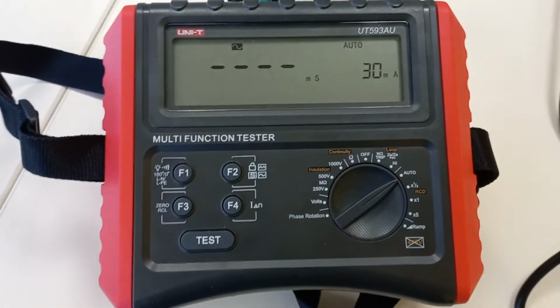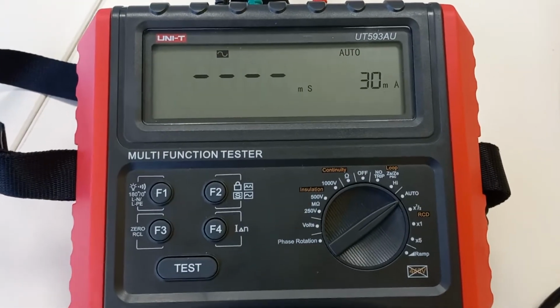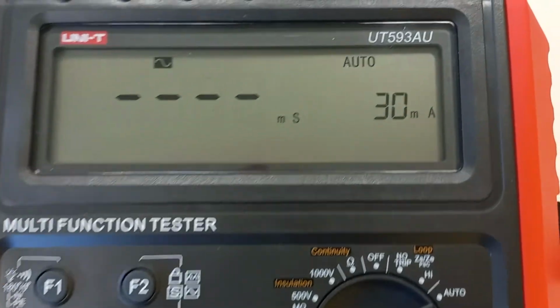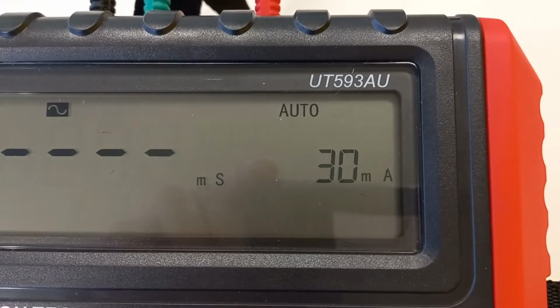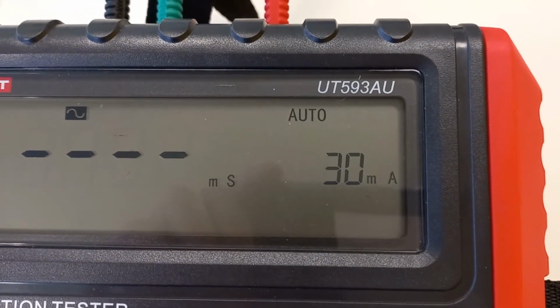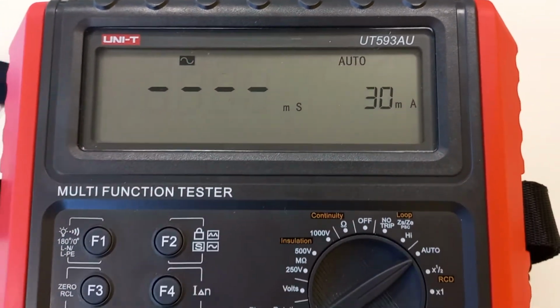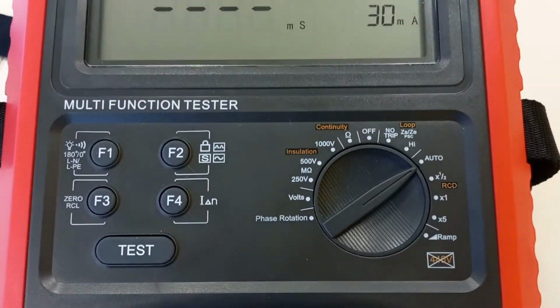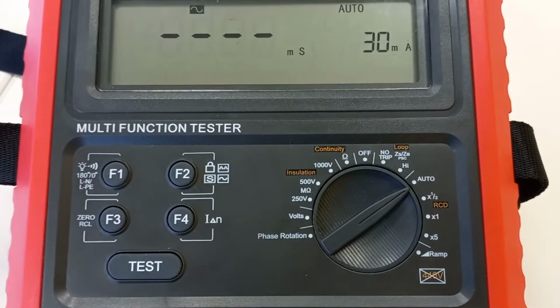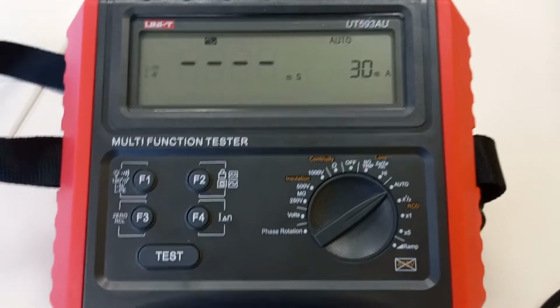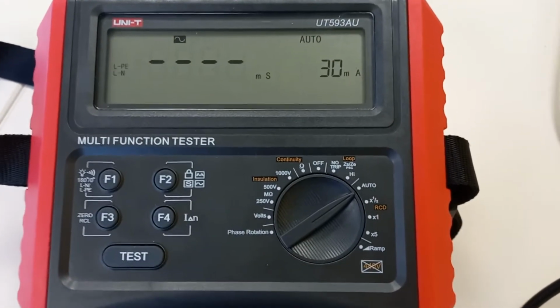The instrument I'm going to use for testing this RCD is the UniT multifunction tester model UT593AU. I'm going to use the auto function and show you how this meter stacks up for this test.